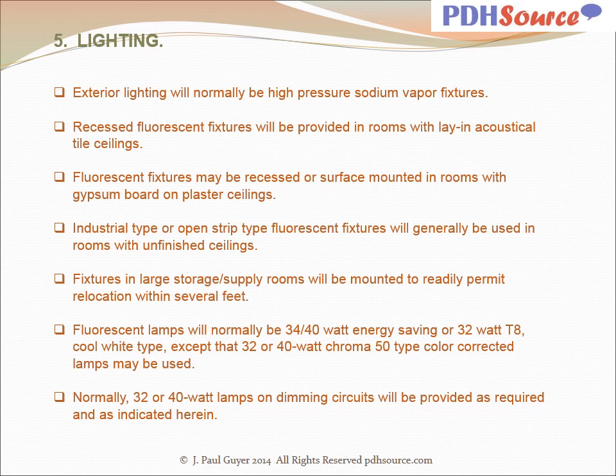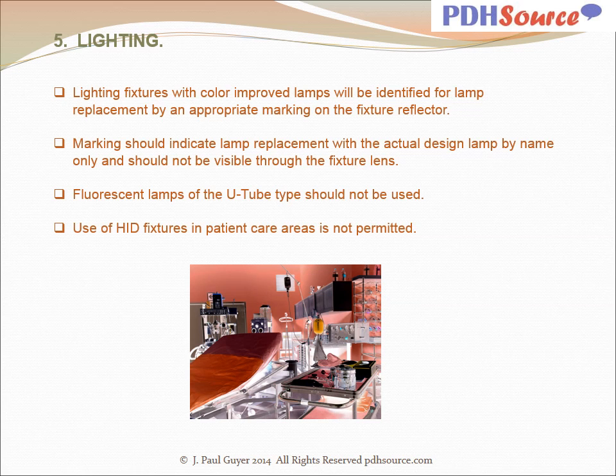Fluorescent lamps will normally be 34 or 40 watt energy saving or 32 watt T8 cool white type, except that 32 or 40 watt Chroma 50 type color corrected lamps may be used. Normally, 32 or 40 watt lamps on dimming circuits will be provided as required and as indicated herein. Lighting fixtures with color-improved lamps will be identified for lamp replacement by an appropriate marking on the fixture reflector. Marking should indicate lamp replacement with the actual design lamp by name only and should not be visible through the fixture lens. Fluorescent lamps of the U-tube type should not be used. Use of HID fixtures in patient care areas is not permitted.